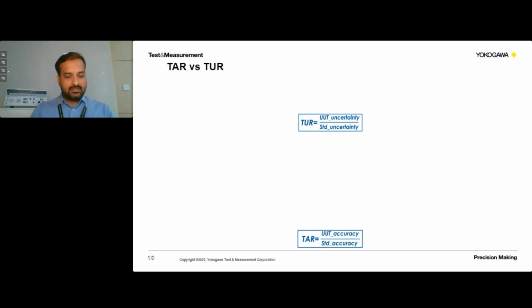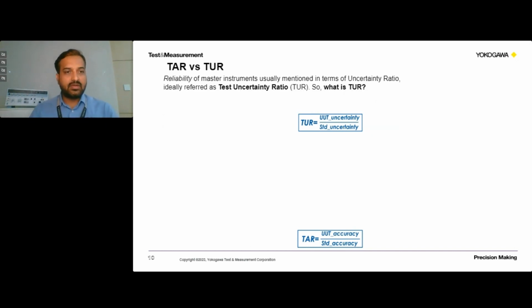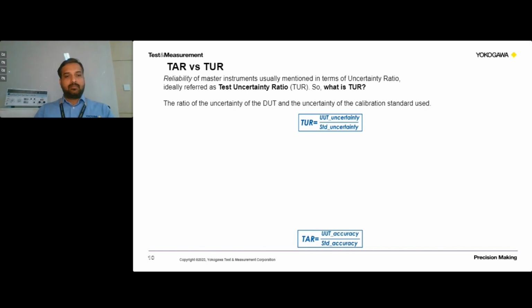Usually uncertainty will be measured like test uncertainty ratio. Test uncertainty ratio is the uncertainty of the DUT compared to the uncertainty of the standard we are using. So the reliability of the master instruments is usually mentioned in terms of test uncertainty ratio, and TUR will be defined as the uncertainty of the DUT to the uncertainty of the standard we are using.